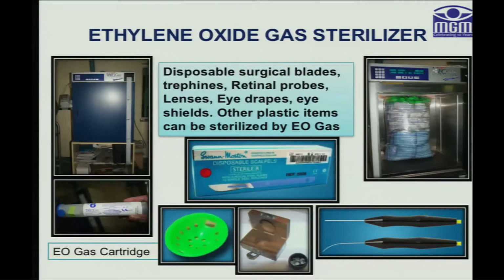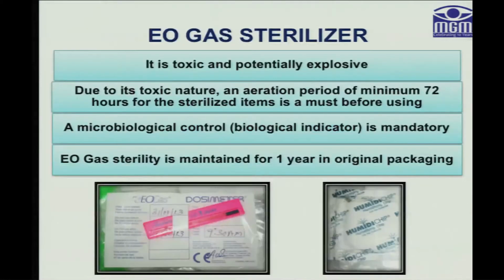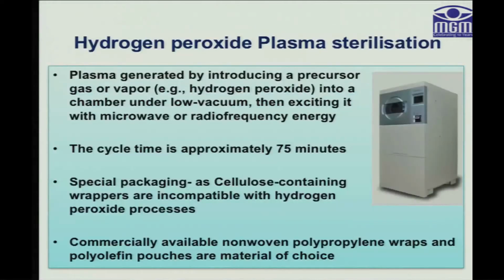Ethylene oxide gas sterilizer can be used for disposable surgical blades, retinal probes, lenses, eye drapes, eye shields, and other plastic items. We know that it is toxic and potentially explosive, so due to its toxic nature, an aeration period of minimum 72 hours for the sterilized items is a must before using. A microbiological control is mandatory, and this sterility is maintained in the original packing.